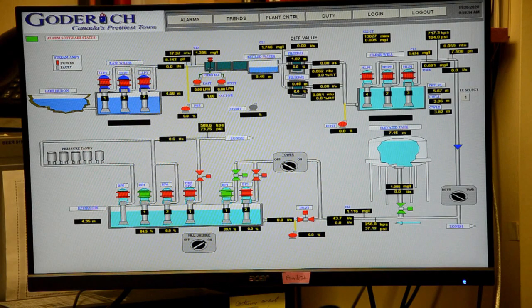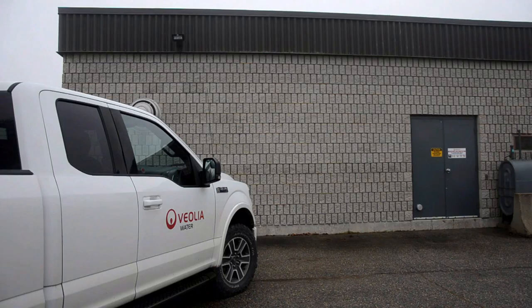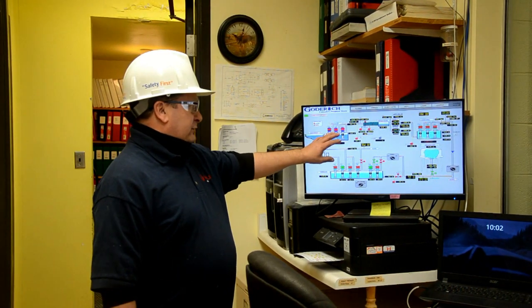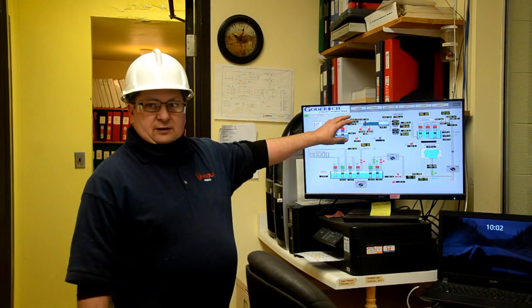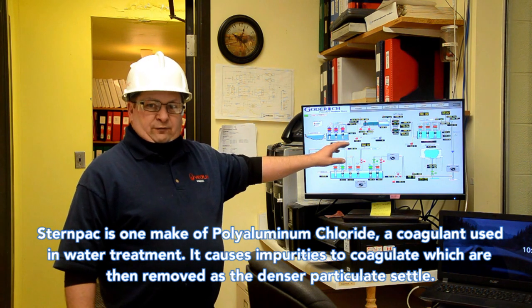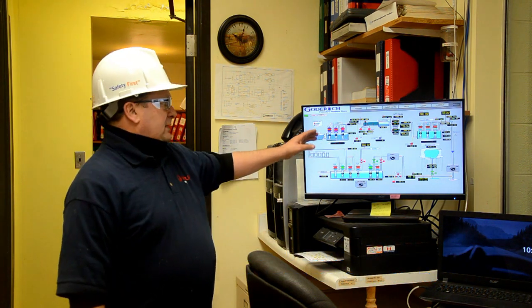This is the SCADA system we use to operate the water treatment plant in Goderich. It basically tells the story from the water entering the plant, how it's going through the plant, and right up until when it leaves and flows over to the booster station. As the water comes into the water treatment plant, it monitors things like turbidity, pH, and temperature of the water. It also shows dosage rates used for SternPAC, fluoride, and chlorine.